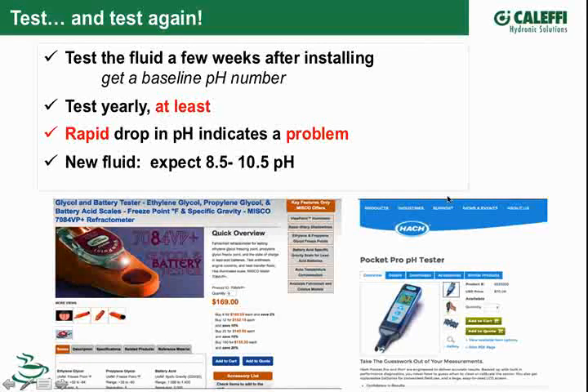The refractometer is a good way to verify you've got the freeze point and glycol concentration you desire - a great, simple tool to test. This one reads both EG and PG on the scale. They usually have a dual screen or dual scale on the viewfinder - you look on one side for ethylene and the other for propylene. So you need to know what fluid you put in there; it can't tell the difference, but it can tell you what the freeze point will be for either fluid.